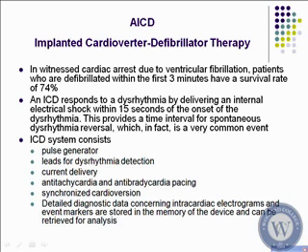Some of them, I've actually seen them want the AICD pulled out. They said, I don't want to feel that. I'd rather be dead. That's what I've been told. So it's interesting. The AICD consists of a pulse generator and leads for dysrhythmia detection. It looks like basically a normal pacemaker. Okay? It has anti-tachycardia and anti-bradycardia pacing protocols in it. It does synchronized cardioversion as well.